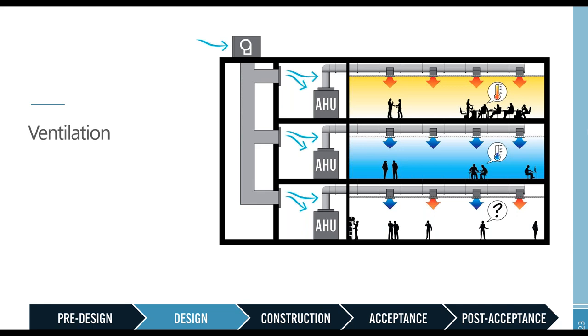This is a great way to save fan energy in general. But reading further into the sequence, the designer called for the rooftop ventilation fan to control its speed to a static set point just below a duct's pressure rating, and for the mechanical room dampers to open fully during operation.